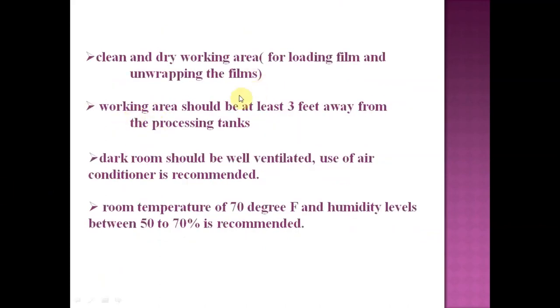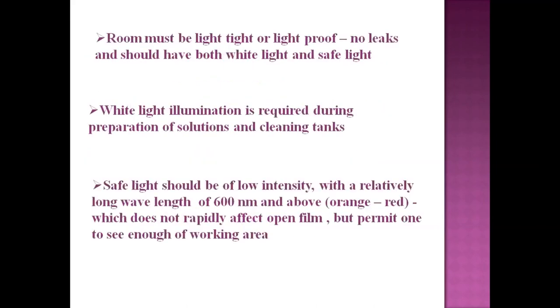Usually three by three feet for an individual dentist and 16 to 20 square feet for a group practice. The working area should be clean and dry, at least three feet away from the processing tanks. The dark room should be well ventilated; use of air conditioning is recommended. Room temperature should be 70 degrees Fahrenheit and humidity level 50 to 70 percent. The room must be light-proof with no leaks, and should have both white light and safe light.